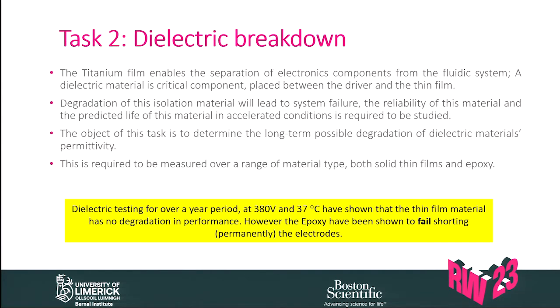The second test was the dielectric breakdown. So these metal foils are the interface between the fluids that are flowing in the device and all the electronics. But obviously it's a metal. That means that it's not insulating the fluid from the electronics. For this reason, there will be an insulating layer to actually insulate the fluid from the electronics. So it's key to understand if this thin insulation layer will degrade, will break, what's going to happen under stress conditions and high temperatures. So we tested with higher applied static voltages and at 37 degrees.